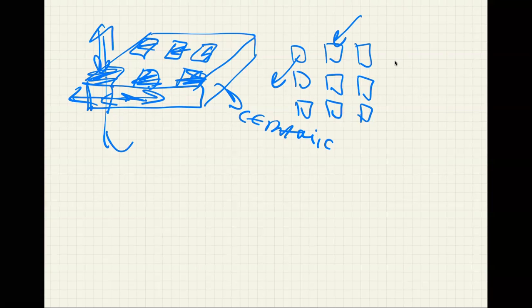So to avoid that, you either use materials that have a very low transverse piezoelectric coefficient, such as lead titanate, but that's not very practical. Still, there would be a lot of leaking of a signal. One way to avoid that is to put these piezoelectric elements in a polymer matrix, and then the polymer matrix will absorb all transverse signals.